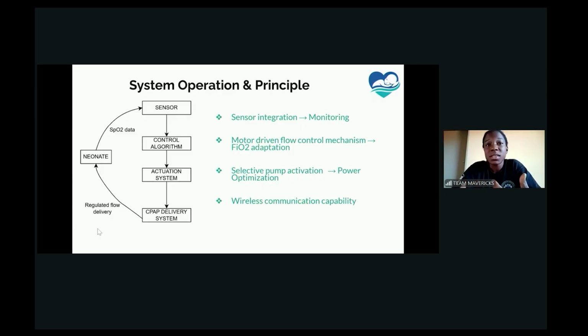The core principle of our system lies in its closed-loop autonomy to reduce dependence on manual intervention. By receiving data from the sensor module, the control algorithm triggers a precise FiO2 adaptation via the actuator. This sense-and-response mechanism ensures the infant receives regulated flow tailored to their physiological needs.